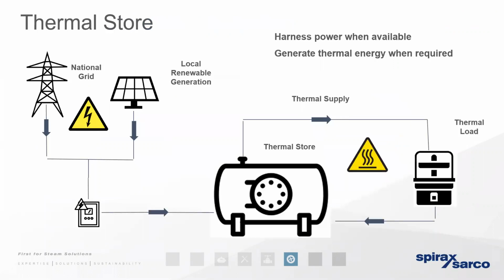But as we mentioned, electrical steam generation still requires a considerable power load. And whilst this is going to have a significant benefit to our clients in reducing CO2, for example, we can take that one step further with the solution that you can see on the screen at the moment. This is what we refer to as the thermal store. And the thermal store can further reduce an electrical demand while still raising steam efficiently.